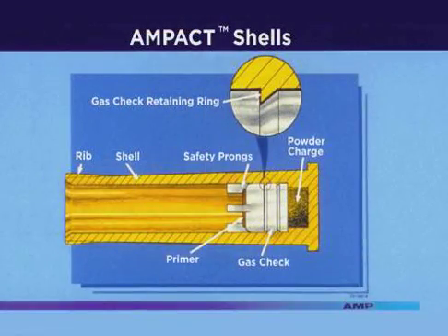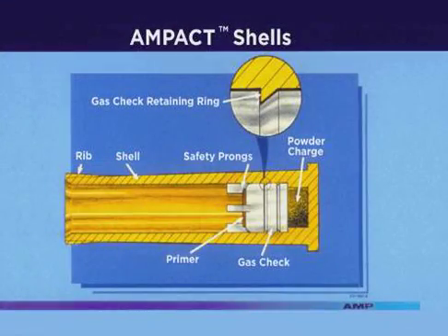This cutaway of the shell will help you better understand its operation. The shell casing is a polyethylene plastic, which contains a retaining ring for the gas check. The primer and powder charge are standard shotgun primer and powder. The safety prongs isolate the firing pin from the primer until it is collapsed by tightening the tool onto the tap. These shells cannot be used in any type of firearm, and the AMPACT tool will not accept any other type.